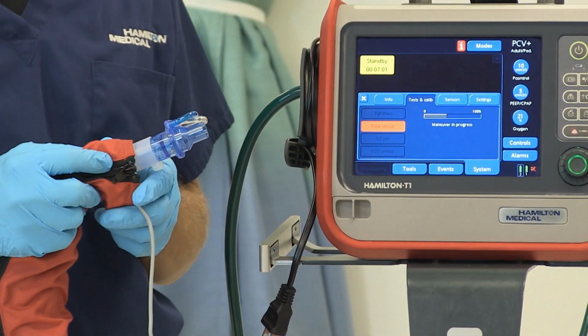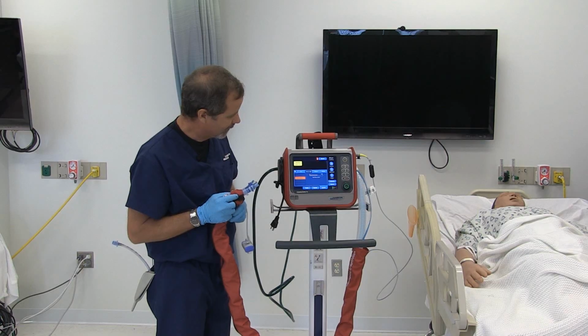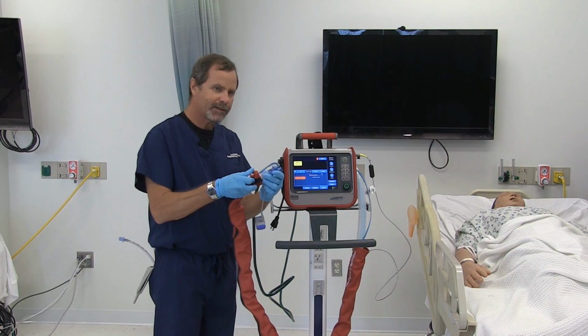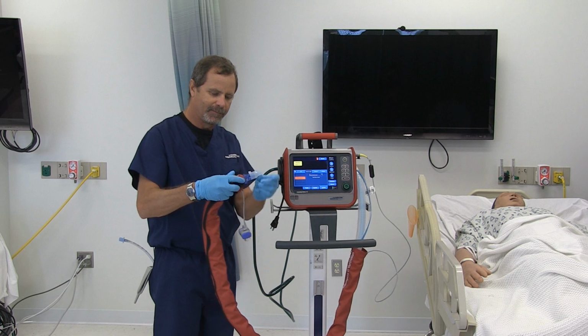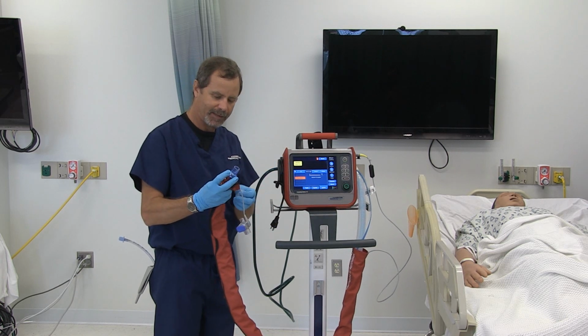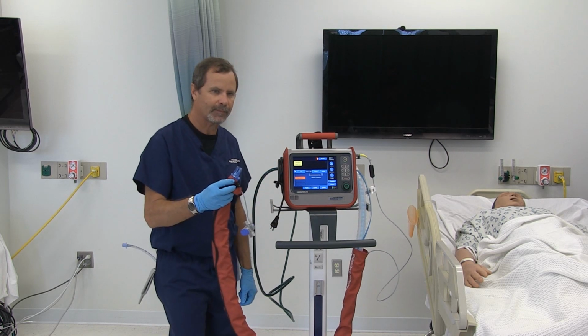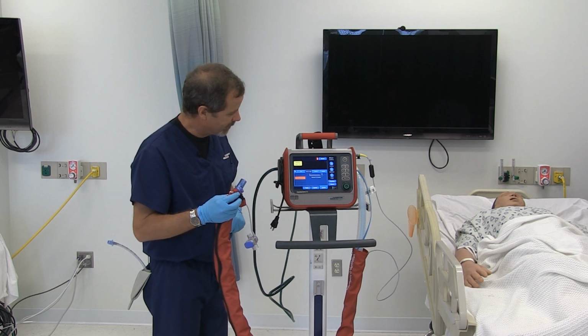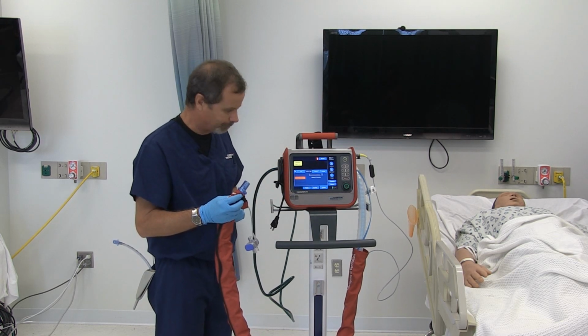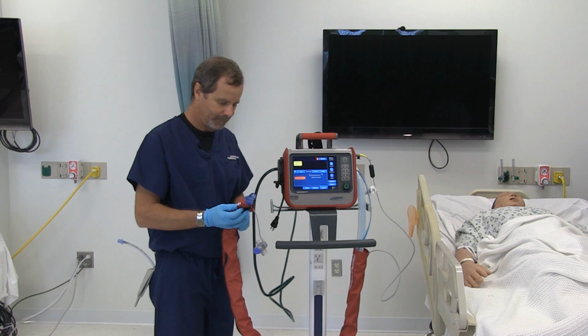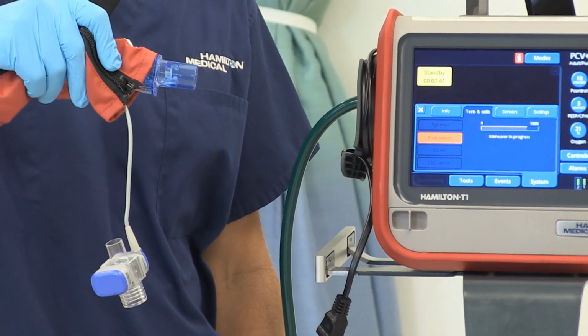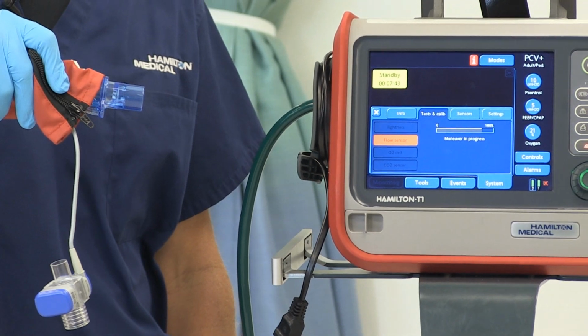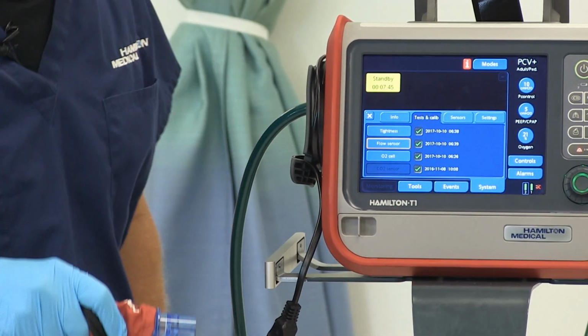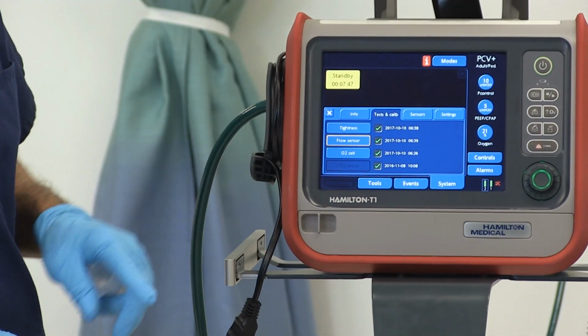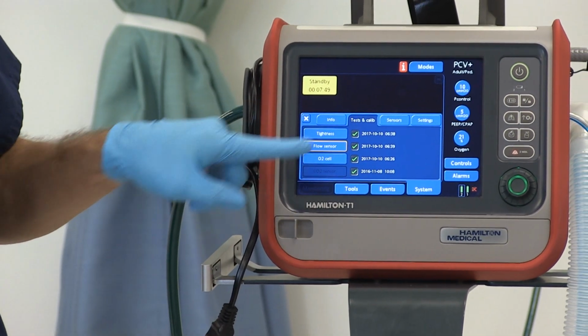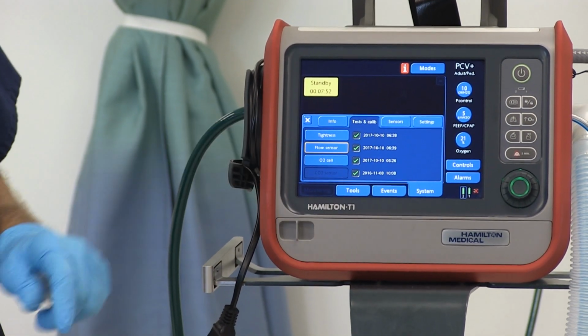Maneuver in progress. Now it tells me to turn the flow sensor, so I'm going to reverse the flow sensor. I'm not going to remove the adapter because it's no longer needed. Watching the screen, you can see it's going to go through the maneuver again. Okay, the test has been completed. We can confirm with a green check mark and the time and date stamp on both of those tests.